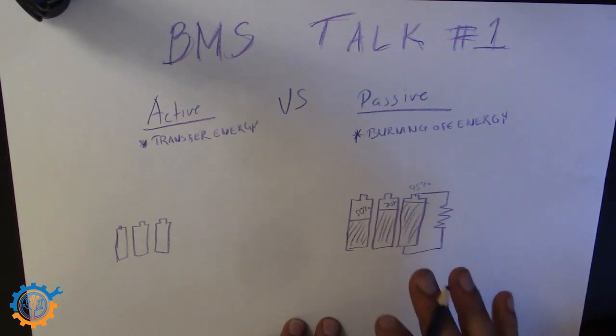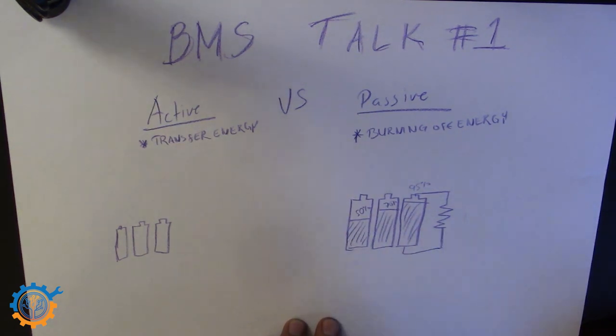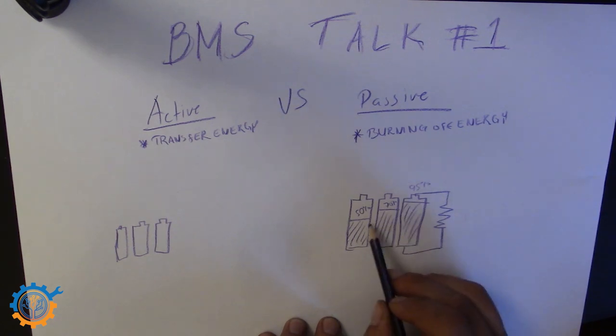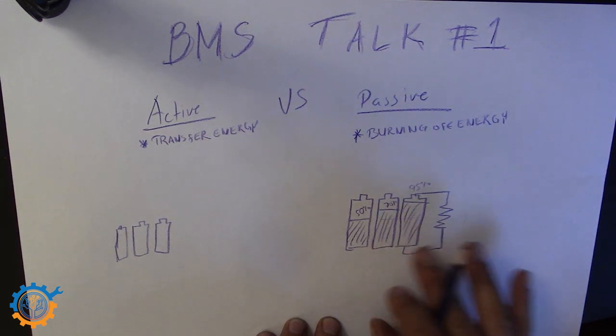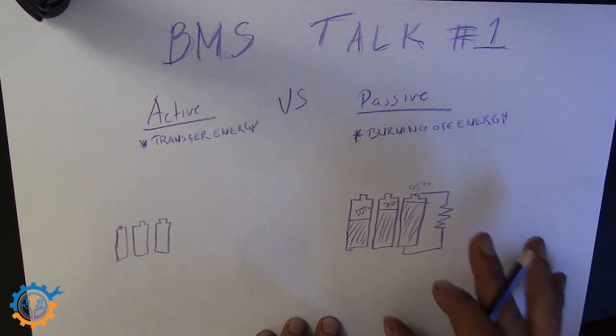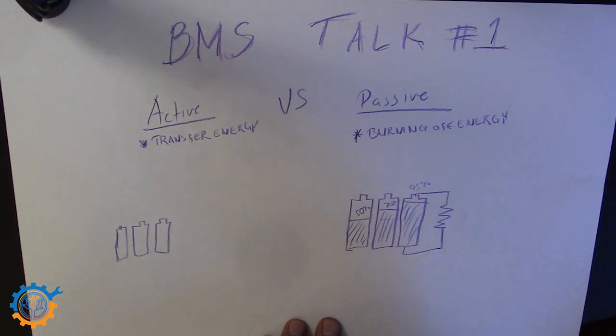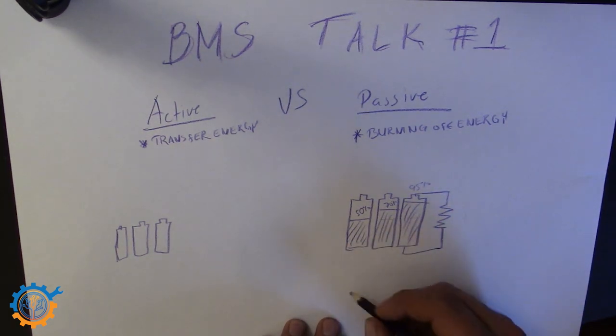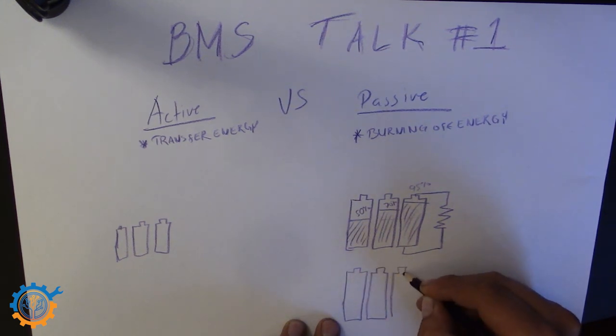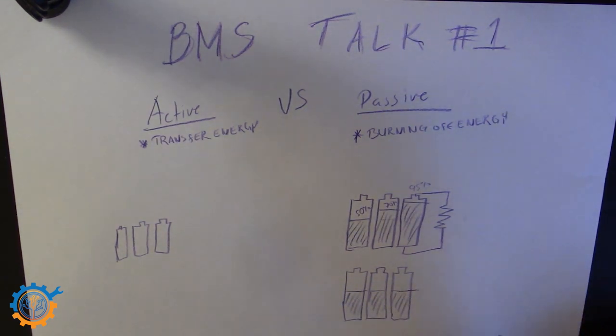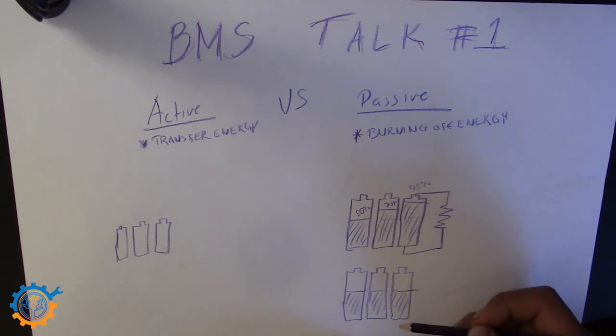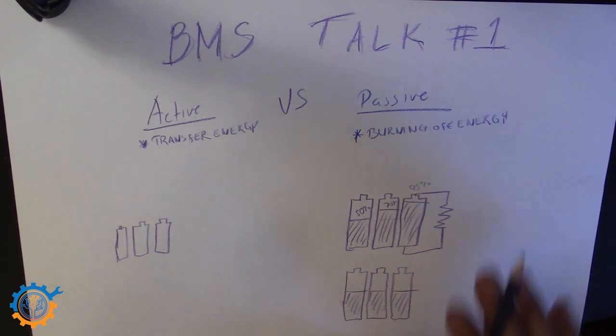You will be burning off energy in the beginning until you have all cells aligned at 50%. This initial balancing takes some time and will burn off excess energy. But when you already have everyone aligned properly, everyone is at 50%. When you start to charge, they should stay consistent both at the top and bottom if the capacity of the cells is the same. If the capacities aren't the same, they will vary.